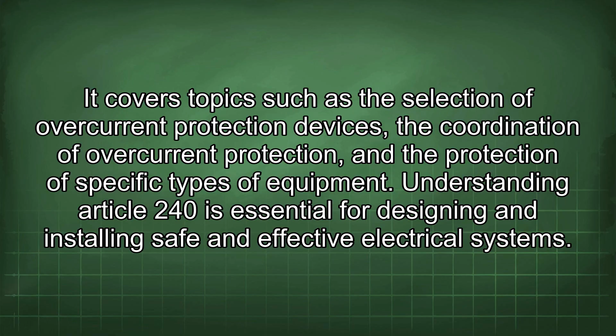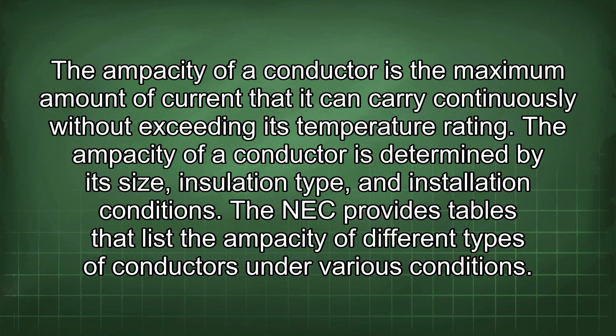The ampacity of a conductor is the maximum amount of current that it can carry continuously without exceeding its temperature rating. The ampacity of a conductor is determined by its size, insulation type, and installation conditions. The NEC provides tables that list the ampacity of different types of conductors under various conditions. It is important to select conductors with an ampacity that is sufficient to carry the expected load current, taking into account any applicable derating factors.